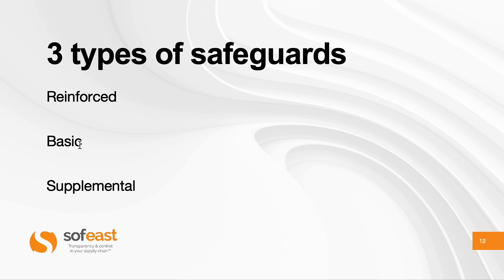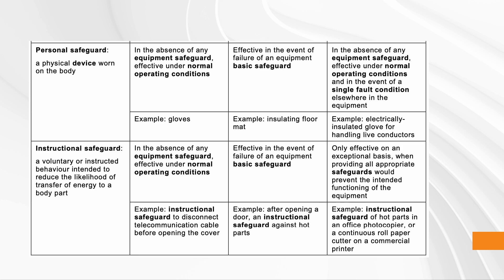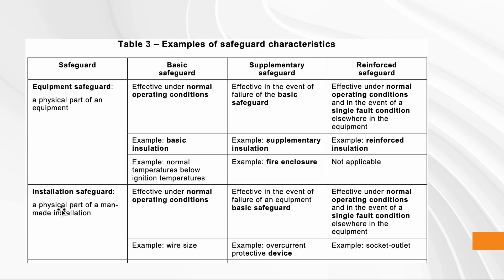In some cases, a reinforced safeguard can be replaced by a basic plus supplemental safeguard. The standard provides Table 3 showing different kinds of safeguards from most effective to least effective. If you just provide instructions, you're hoping people will read the user manual. If you count on people to wear personal protective equipment, you're relying on them to take action. If you require companies to install something during product setup, that's also a dependency.